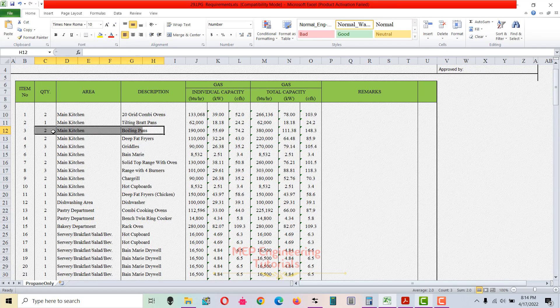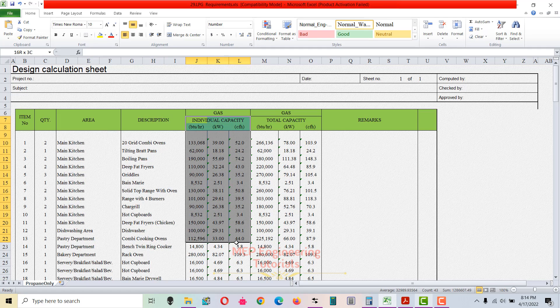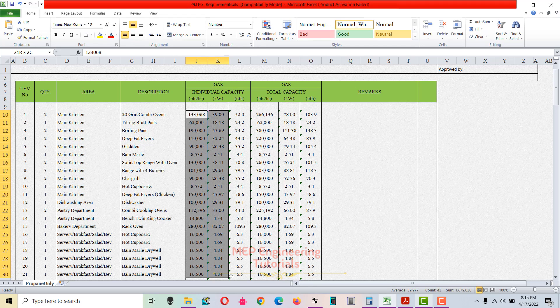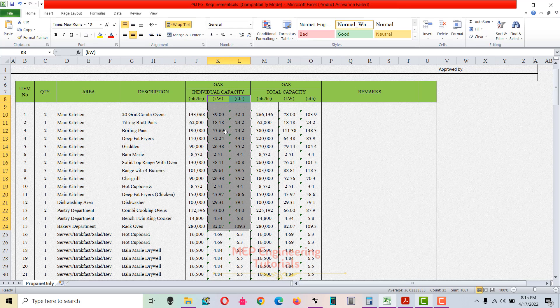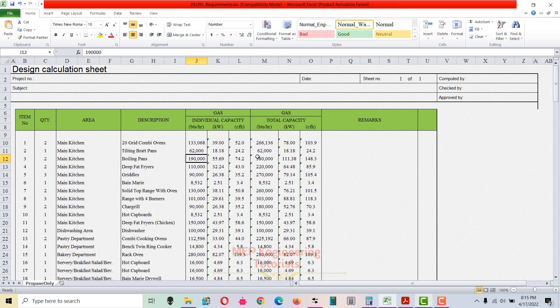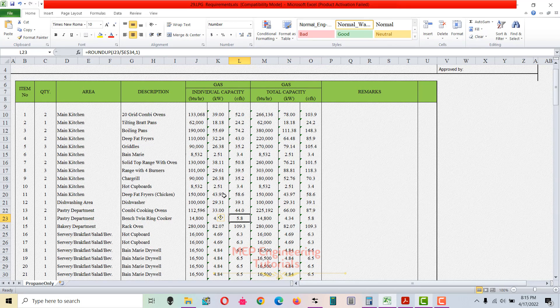For example, in the main kitchen you have two boiling pans, so you write two in the quantity column. Then you write the capacity of each equipment serving in that area. You get these capacities from the supplier who supplied the kitchen equipment — they will provide values in BTUs per hour. This is just a conversion for kilowatt and CFH, and this is the total capacity of that equipment. Since we have two boiling pans, we multiply by two to get the total capacity.